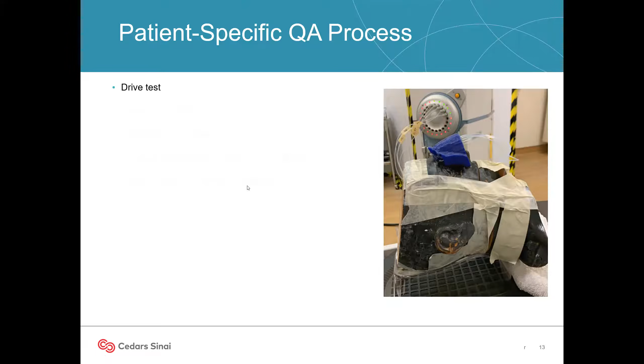So after the mold is prepared, we then deliver a test plan that drives the source positions to the end of each channel to ensure deliverability. And there's an example picture of that shown here. We also try and put it in a similar orientation that it will be on the patient when they're treated. We actually did catch an issue with one mold by doing this, and it was a nose mold. And what happened was that it wasn't the path inside the mold, but rather the way we had glued the catheter, and it was a little bit too extreme of a bend right at the base of the mold. And so this was a really easy fix by just removing the glue, since you can snap it off with a little bit of force, and re-gluing it so it had a less extreme angle.